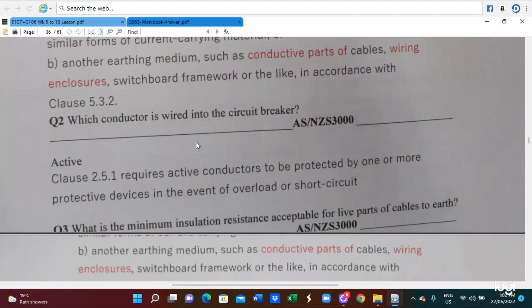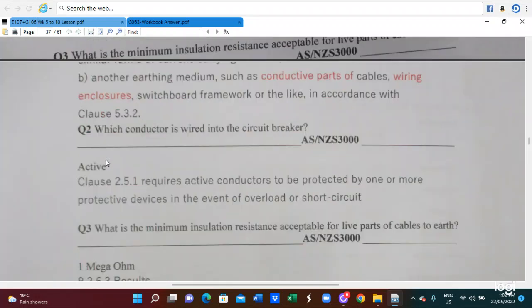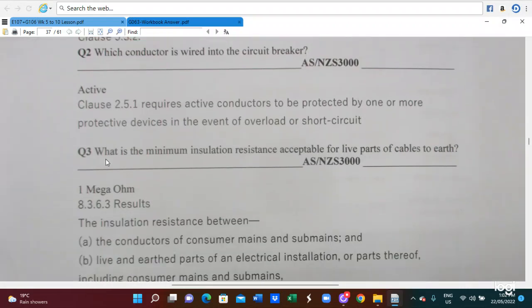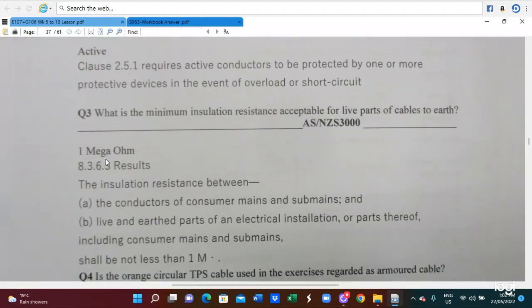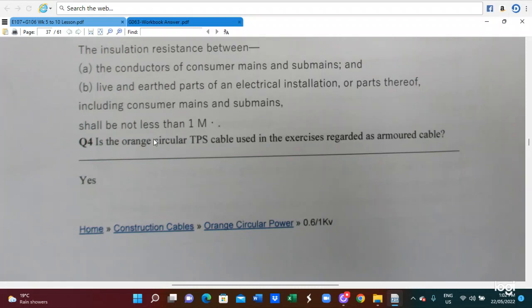Question 2 is which coded wire goes into the circuit breaker. In this case, we have to use an active wire, cross reference 2.5.1. And also question 3, what is the minimum insulation resistance acceptable for the cable? In this case, it is 1 megaohm, cross reference 8.3.6.3. It must be 1 megaohm.